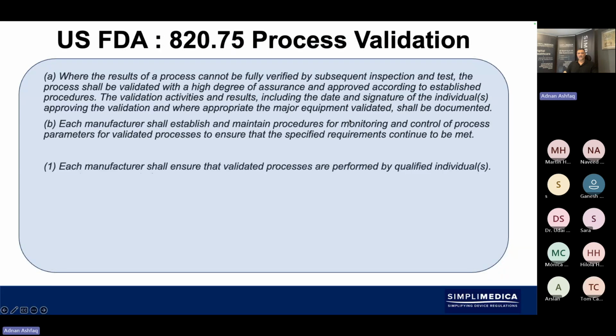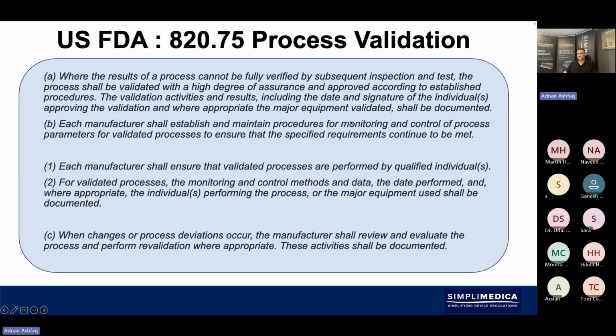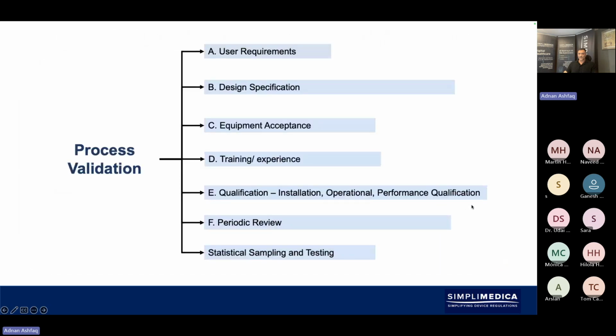We also then have the US FDA 820.75, the FDA's process validation definition. I'm not going to read this in its entirety. It's there. You can take the reference. 820.75 is the process validation clause from the FDA Part 820. And as most of you know, the FDA are now also recognizing the QMSR, which is the ISO 13485. So the definition that we looked at in slightly more detail prior to the FDA clause is what's going to be explored more even by the FDA. So that 820.75 will ultimately be superseded by the ISO clause 7.5.6.